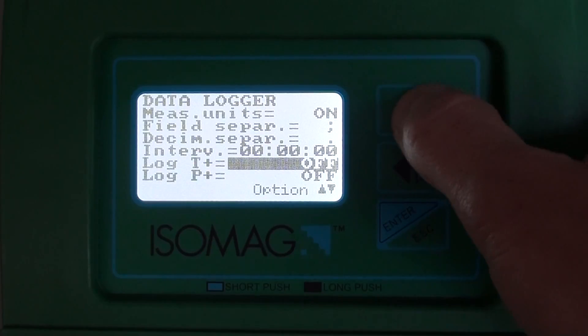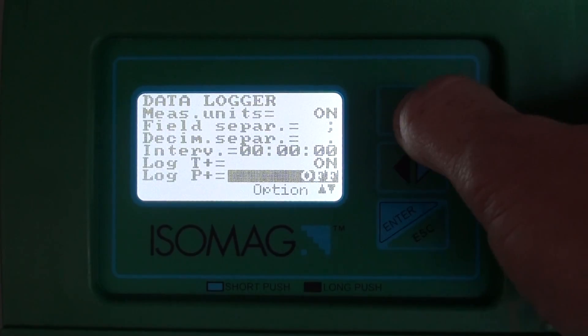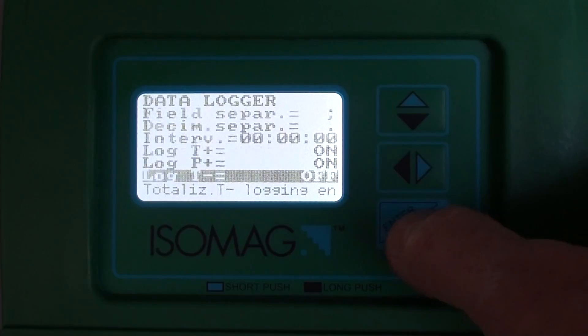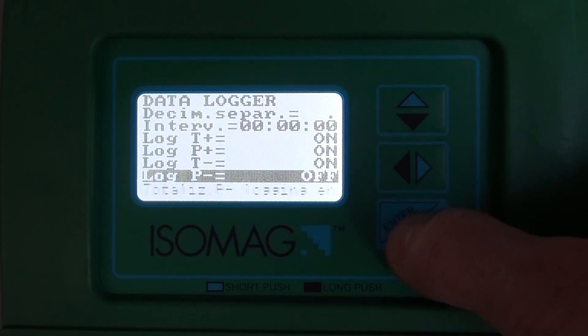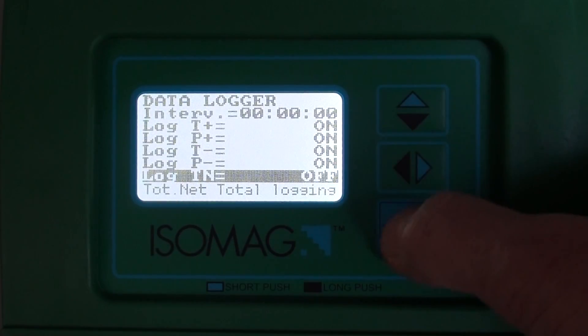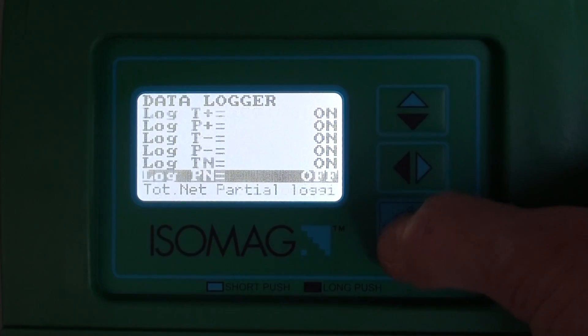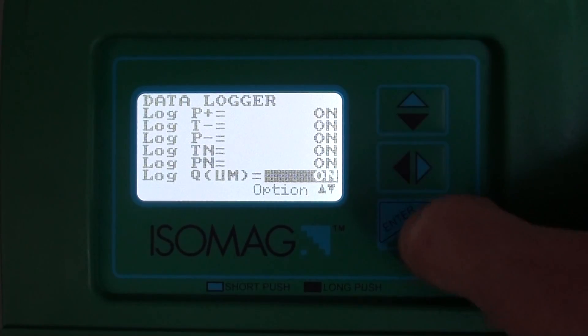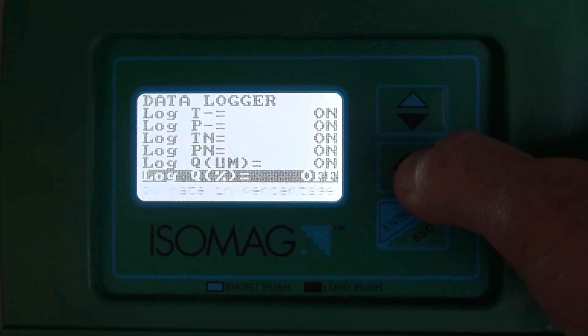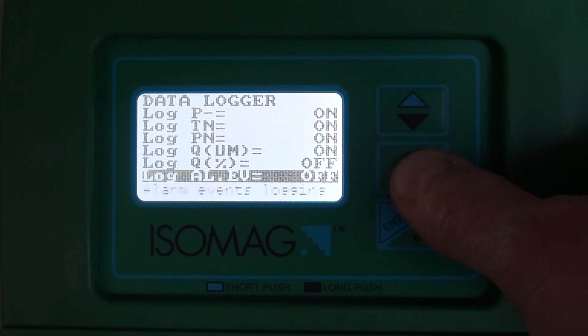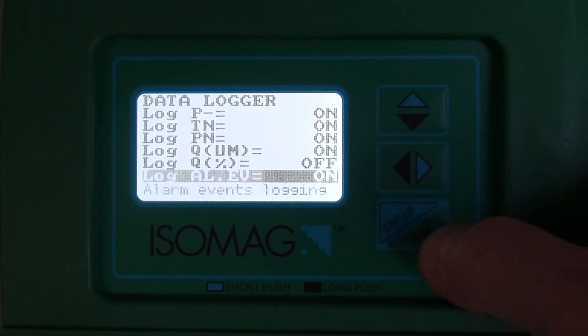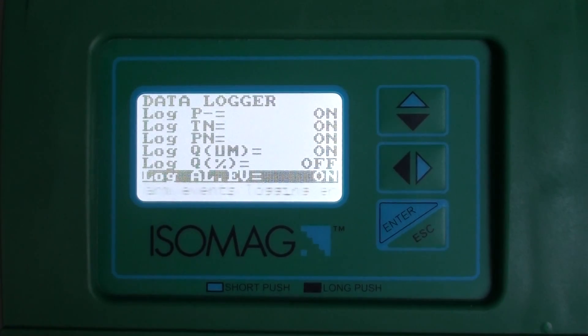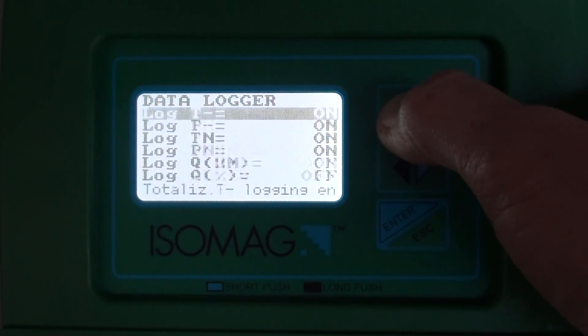In this case I want to log the totalizers: total totalizer positive, partial totalizer positive, the negative totalizer, and the net totalizer. I also want to log flow, and I can choose to log percentages and the number of alarm events that are occurring when the logger makes its logging operation at the interval that we specify.